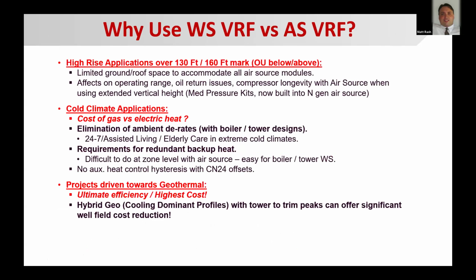Another thing to consider is why use water source VRF versus traditional VRF, if you're familiar with that type of product. This is more important when you start looking at high-rise applications because of limitations on refrigerant lift, the elevation differentials that these systems can accommodate. Cold climates, where you have backup heating needs in the zone, especially with electric, not only is that costly, but it can introduce comfort issues because there's a hysteresis there with regard to operating backup heat with air source product. And then really, the subject that we're focused on here today is ultimate efficiency. That's going to be in that geothermal realm, where projects are mandating it, and water source VRF again brings that capability to achieve that, with some added benefits with optimized heat recovery.